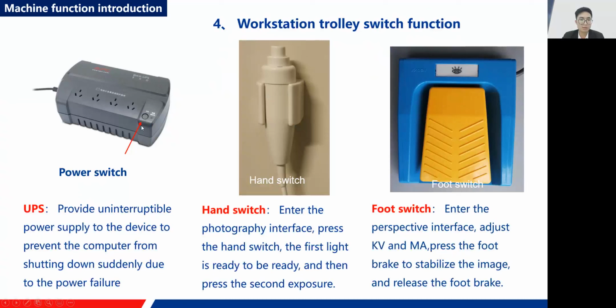Okay, and 3 parts. One part, the power switch of the UPS. Of course, UPS stands for uninterruptible power supply, and it provides uninterruptible power to the device. Here it provides the power for the 2 screens, the main screen and the reference screen. And the image intensifier is also powered by this. And of course, our computer is powered by the UPS, so it provides power to all these 4 devices, right? 2 screens, 1 image intensifier, and 1 computer.